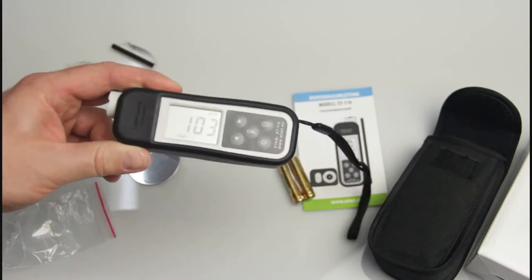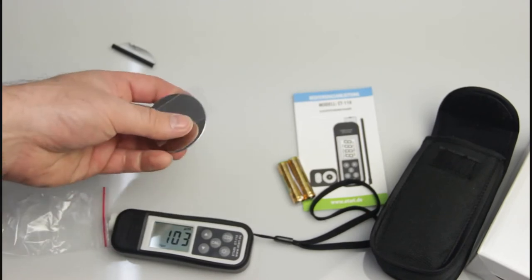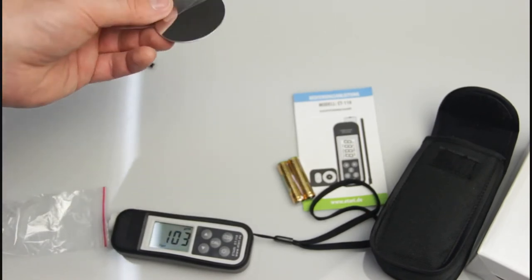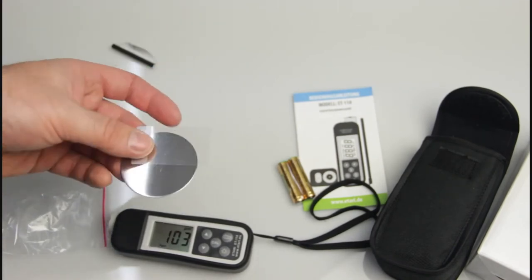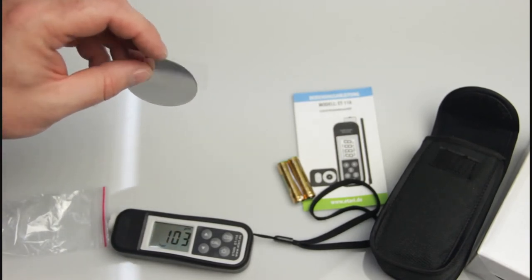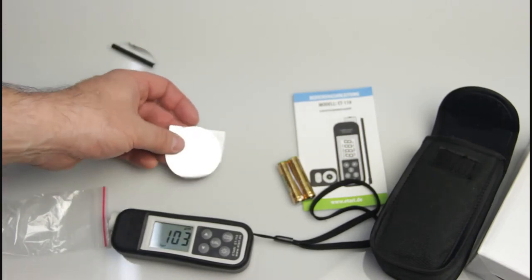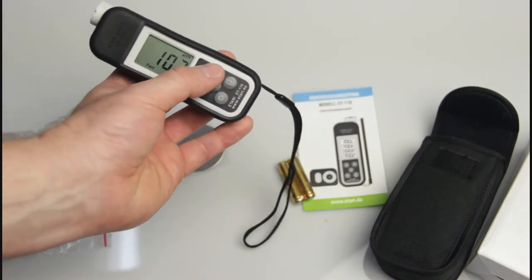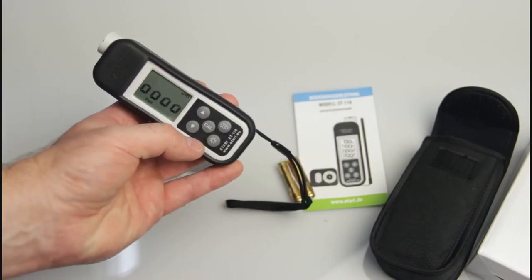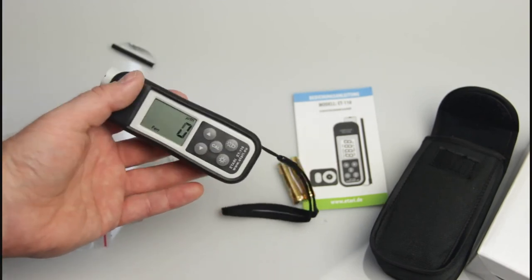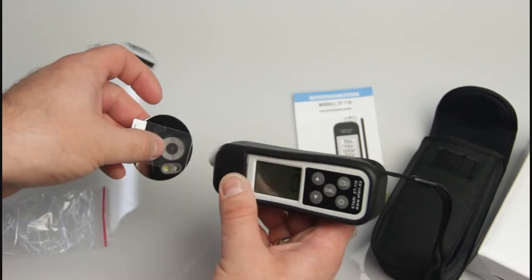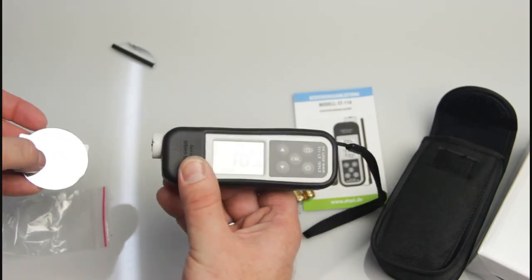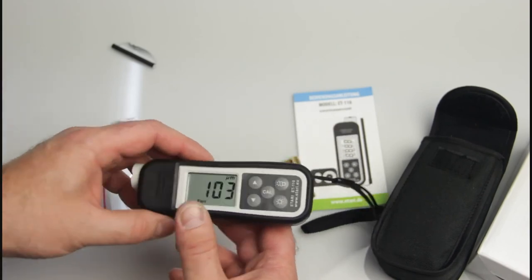This feature was made for automotive professionals who carry this every day. Let's say you forgot the calibration set somewhere or it becomes scratched and you're not sure that the thickness of this plastic layer is really good to calibrate the gauge. If you're not sure, just press it and auto-calibrate it. Let's check one more time. The difference is only 1 micron, as you see.